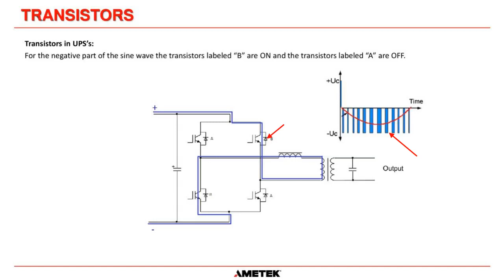For the positive half of the sine wave, we switch IGBTs on and off to create that pulse width modulation, and for the negative portion, we switch IGBT pair B on and off. Some clever person came up with this H-bridge configuration, and power flows along here, making this side of the transformer more positive than the other side, giving us the negative side of the sine wave. Remember, when you don't send a signal to an IGBT, it's open, so no current can flow through these IGBTs without a gate drive signal.